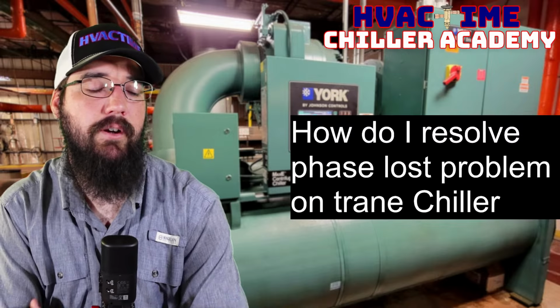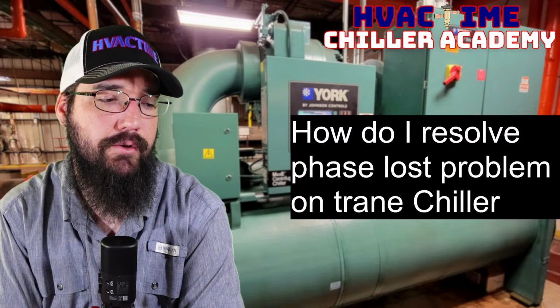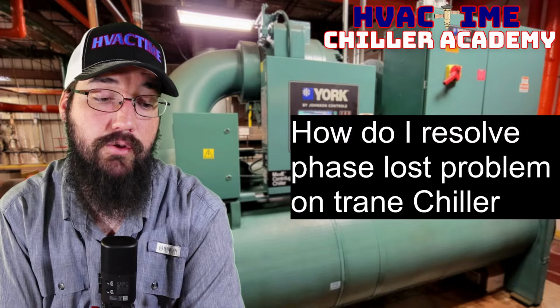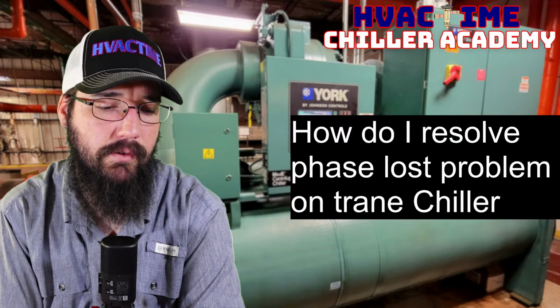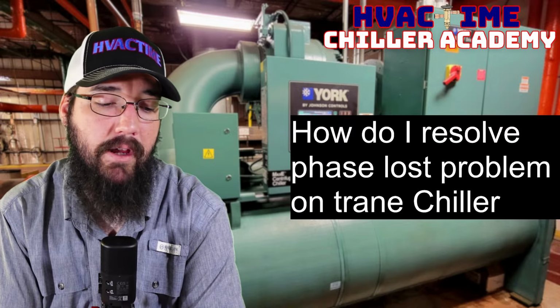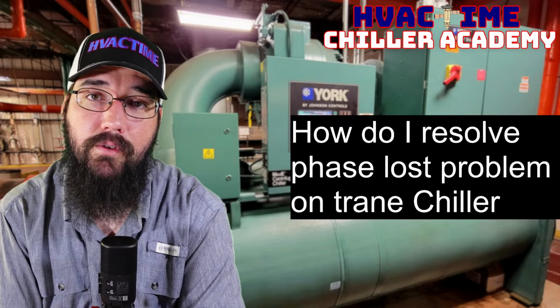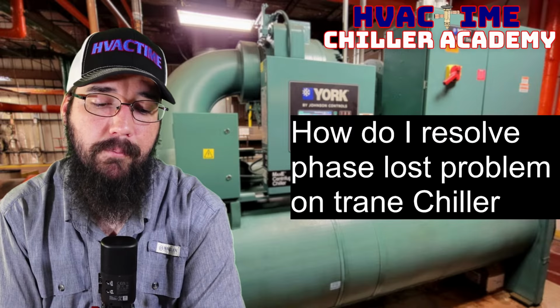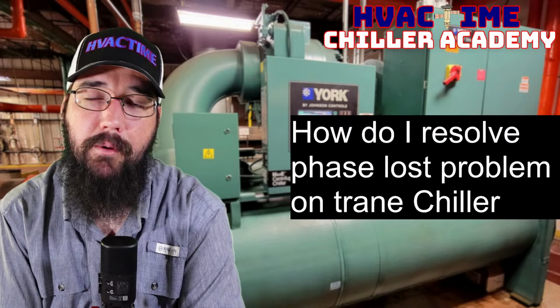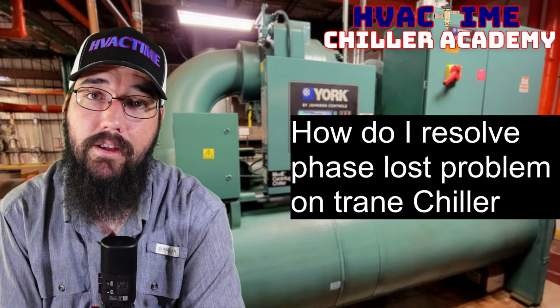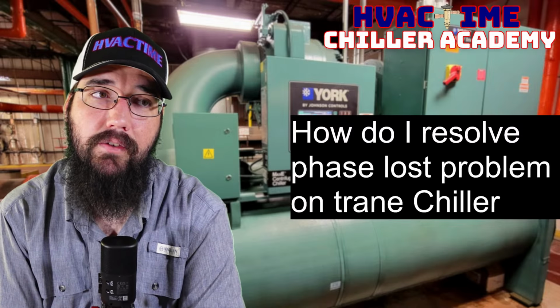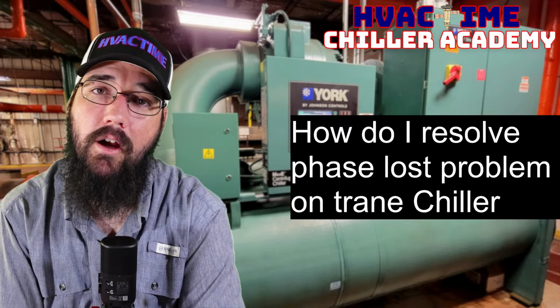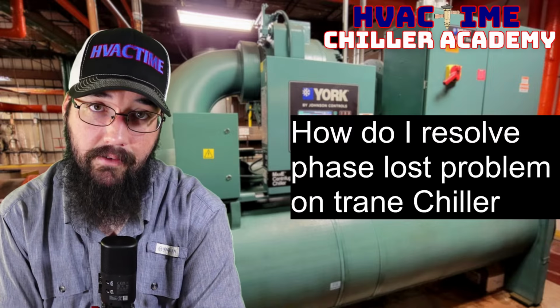Let's see, what all have I ran into? So I've ran into the compressor issue, just reading the voltage or amperage correctly. What else have I ran into? I've had power feed issues from transformers happen. The transformer from the main electrical start got weak, and it wasn't keeping up with the chiller demand. I have had that happen.